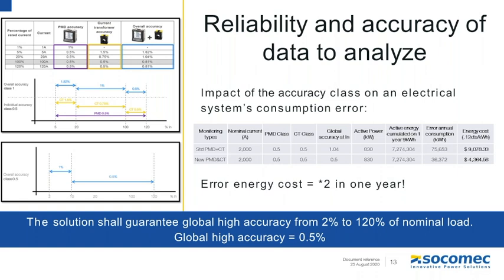In the bottom table, still on the left side, you can see the accuracy of a smart power monitoring devices. The power monitoring device and current transformers global accuracy is 0.5. And it's given and guaranteed by the power monitoring manufacturer. That is a huge difference. And that difference, well, you can see it on the right side, which is a monetary result over a period of 1 year.